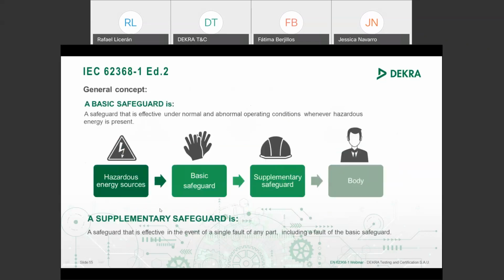Of course, the standard includes double safeguard when it's necessary, and like the 60950 or 60065 standard say, when I have a class 3 of energy, a hazard of energy, the standard requires two levels of safeguard, a basic safeguard and a supplementary safeguard. The definition is very similar to insulation, basic insulation and supplementary insulation. But in this case we speak of safeguard because it is not only insulation.